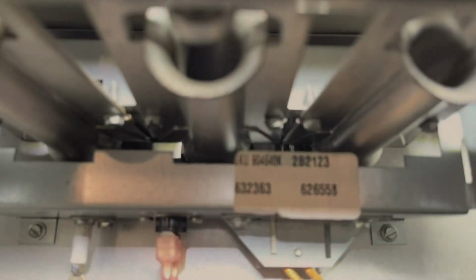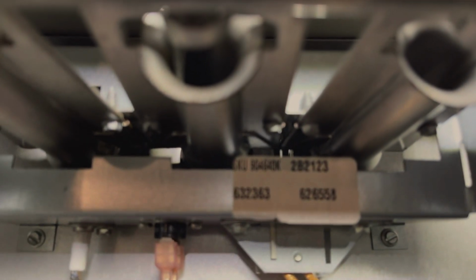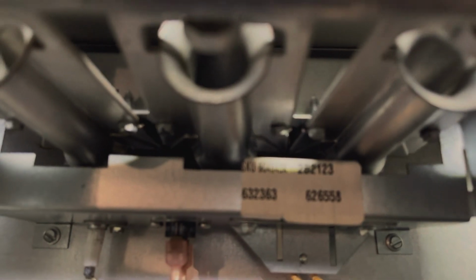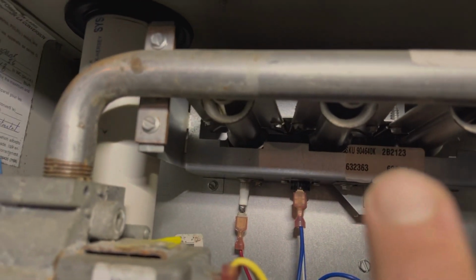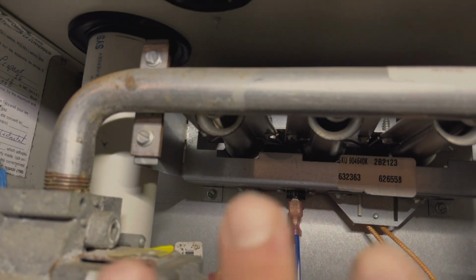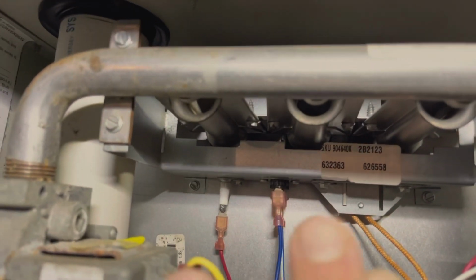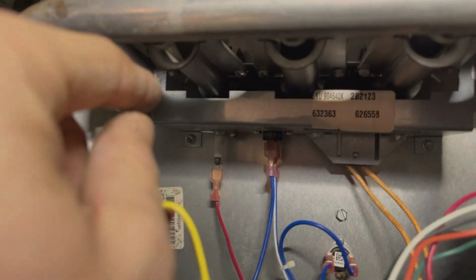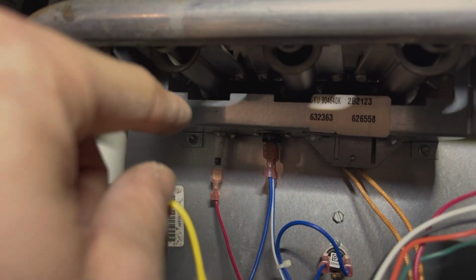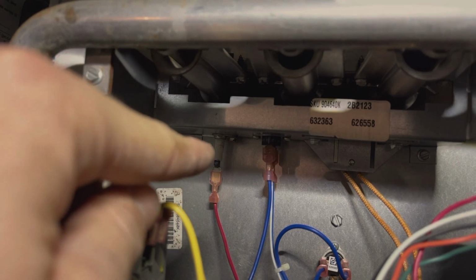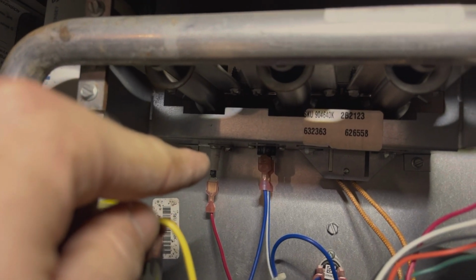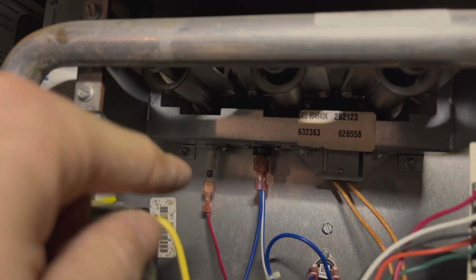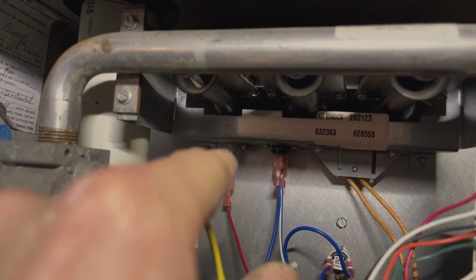This one, it just glows red. I don't know if you can see it there, but it's a little like coil. Once it starts up, you'll see it glowing, and then once it gets up to temperature, then a gas line starts up, and then the igniter you'll hear a little poof. It's okay to have this open when it's starting, and then that'll start up, and then as that starts, your flame sensor will sense the flame. And if it doesn't sense the flame in a given time, then it'll shut it down. So if you have that issue and then it shuts down, it could be that, it could be other things.